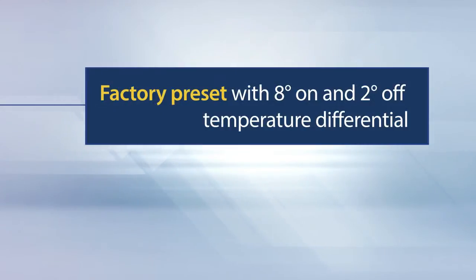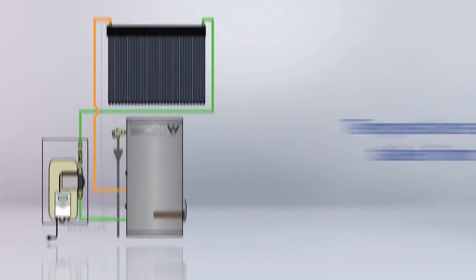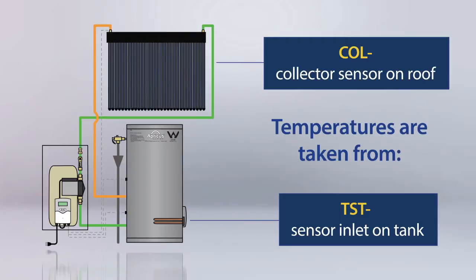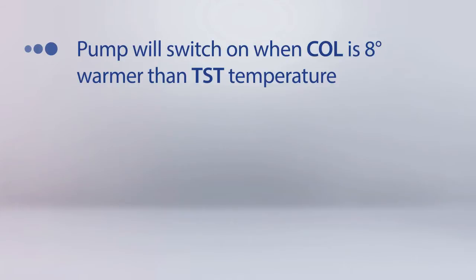All controller settings have been factory preset with an 8 degree on and 2 degree off temperature differential. These temperatures are taken from the sensor inlet on the tank, represented as TST, and the collector sensor on the roof, presented as COL.